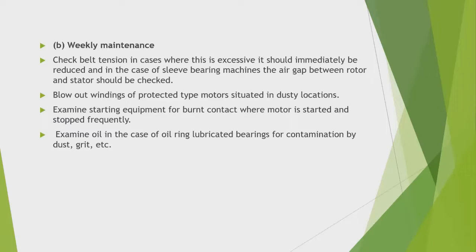Weekly maintenance: check belt tension — where excessive, it should be immediately reduced. In the case of sleeve bearing machines, the air gap between rotor and stator should be checked. Blow out windings of protected type motors situated in dusty locations. Examine starting equipment for burnt contacts where the motor is started and stopped frequently. Examine oil in oil ring lubricated bearings for contamination by dust and grit.